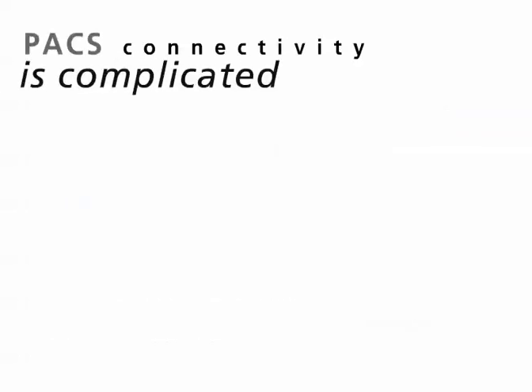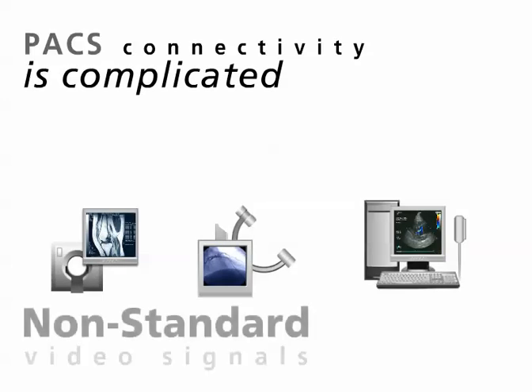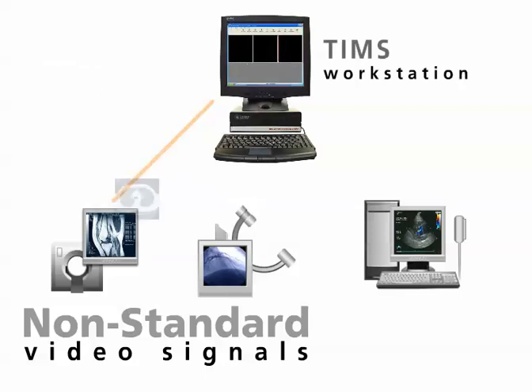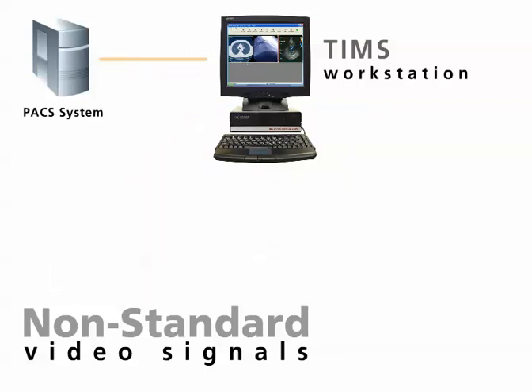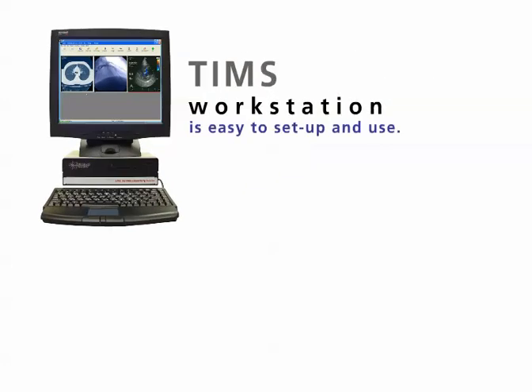PACS connectivity is complicated because many imaging systems use non-standard video signals to produce their pictures. The TIMS workstation has a unique capability to understand any medical video signal and convert it to DICOM. TIMS can work with multiple medical modalities and even quickly switch between modalities. The TIMS workstation is easy to set up and use.